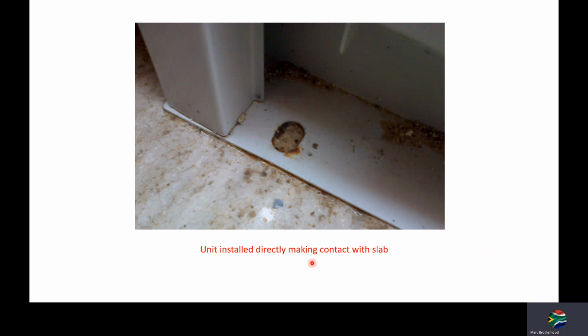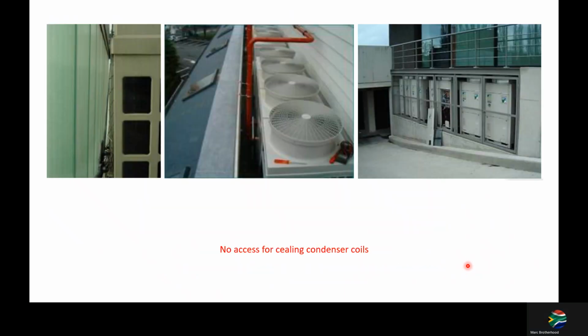Here we can see a unit installed directly making contact with the slab. There's no rubber mounts, and you can already see rust forming. Besides that, there's also going to be vibration transfer into the frame. It's going to be increased noise, rusting of the subframe, as well as the possibility of pipework resonating and creating fissure cracks with time of operating the units.